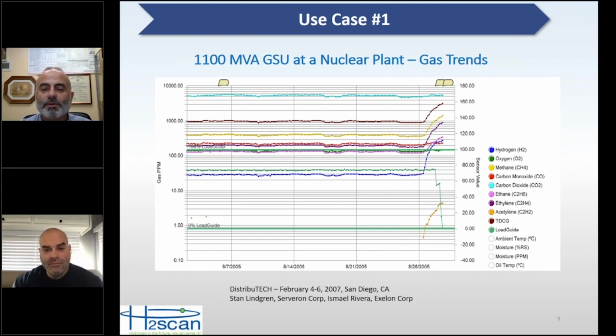Just to show you what happens when you have the online monitoring, this green line here, the middle green line, because there's another one down here, shows the load on the transformer. Within 24 hours after this gassing event started, and it continued because the gases continued to increase, they started pulling the nuclear plant offline, and within 2 days had the plant offline. Because they had the online monitoring, they were able to react very quickly. This could have resulted in a complete transformer failure. And of course, you don't want to risk anything exploding in a nuclear plant, so you get it offline as soon as possible.